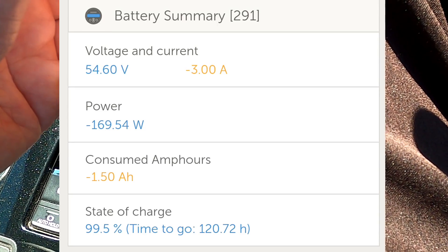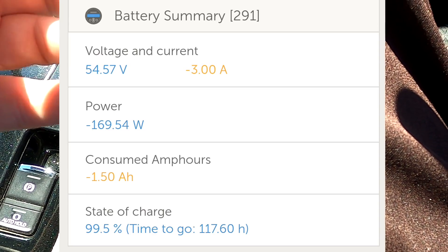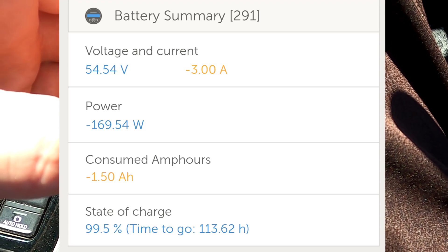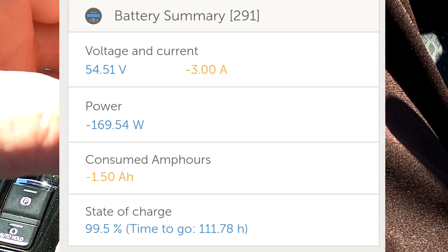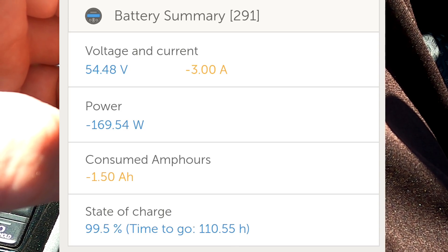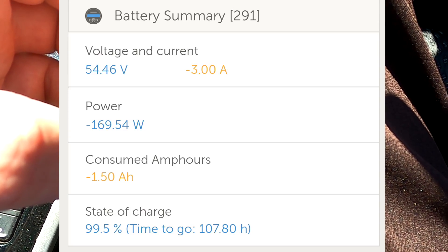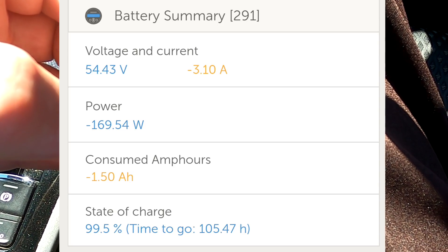As you could see from the screen recording, we just switched to float mode. The battery gets discharged slightly until we hit 53.6 volts which is 3.35V per cell, and we are getting to 99.5%. There is only 1.4 ampere hours missing until real 100% — this is how high you charge if you go to 3.45V and absorb for 15 minutes. So does it make sense to absorb? Absolutely not. You're gaining only 0.3% in capacity.